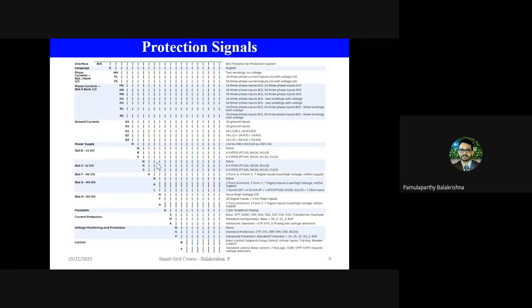So the functions are also designed in a flexible manner so that it can take any form of input that usually exists in any substation. Just by connecting that particular signal to the relay, it will start taking the signal and execute. Whereas in the olden electromechanical relays, you need multiple devices to execute different functions. For voltage and current you would have one device, for temperature another device, for metering another device. You used to have multiple devices connected together to protect a single machine like a transformer. Whereas with a digital relay, it's a single device, a single box, and everything is incorporated into that box. There is no need for any additional box to protect the entire power transformer. That is one of the advantages of this protection relay.